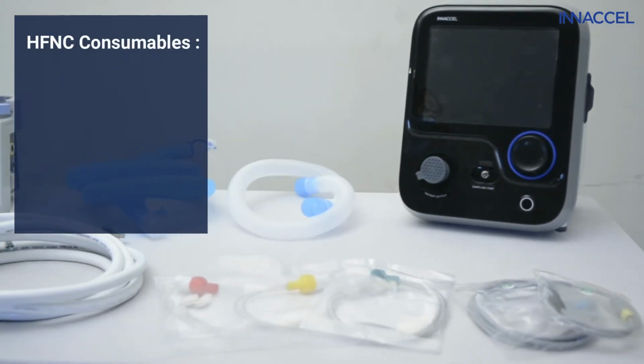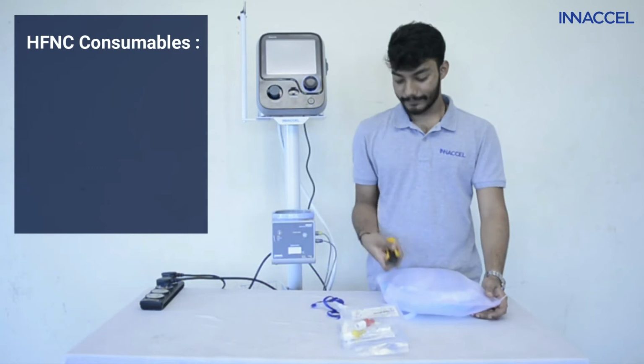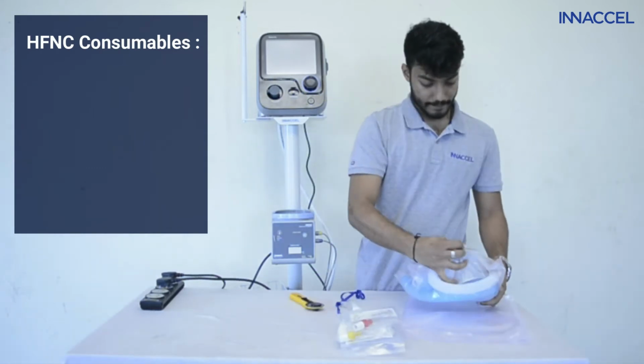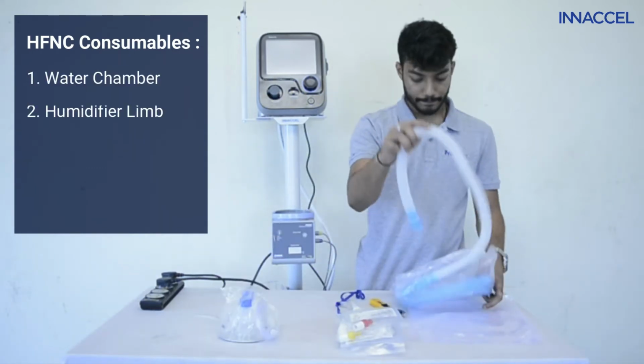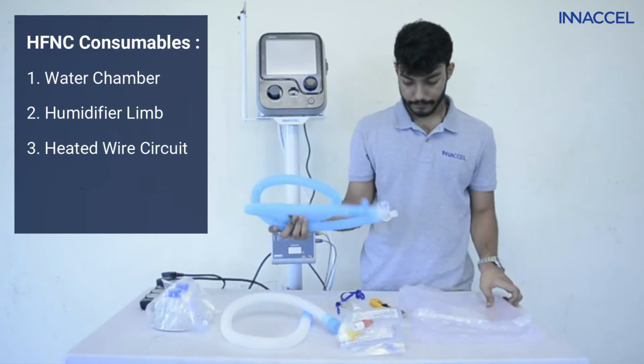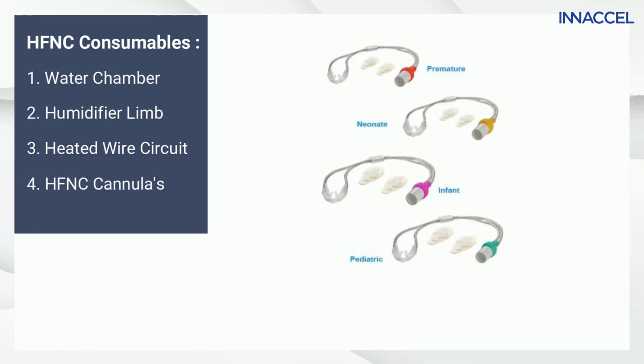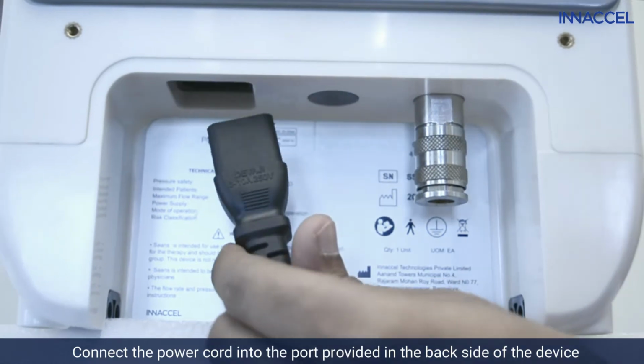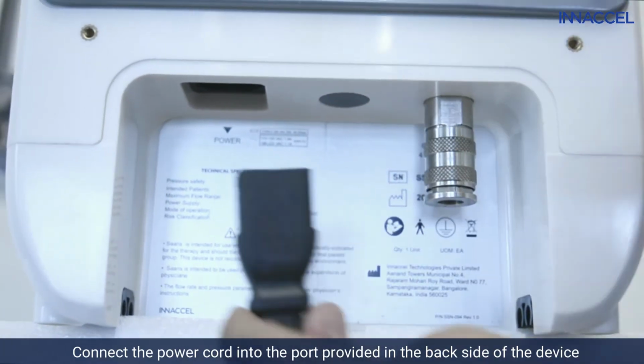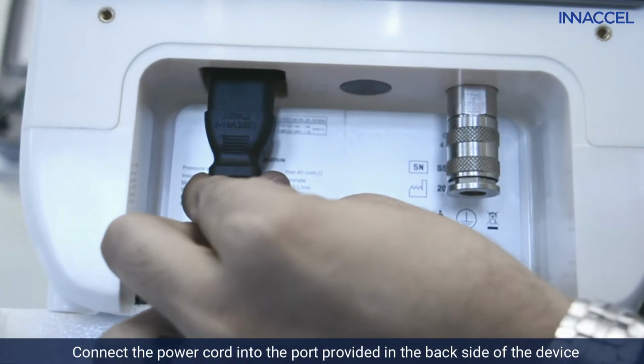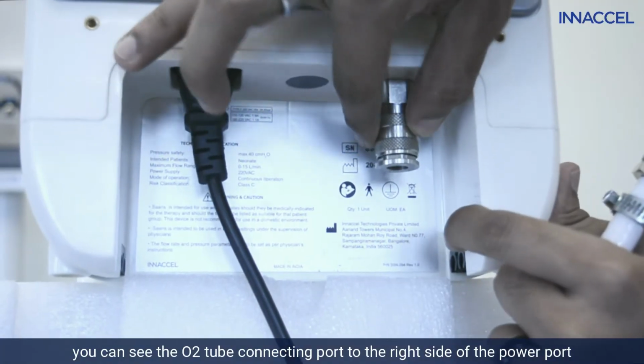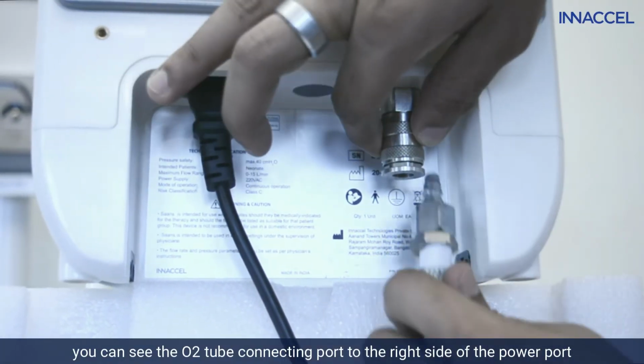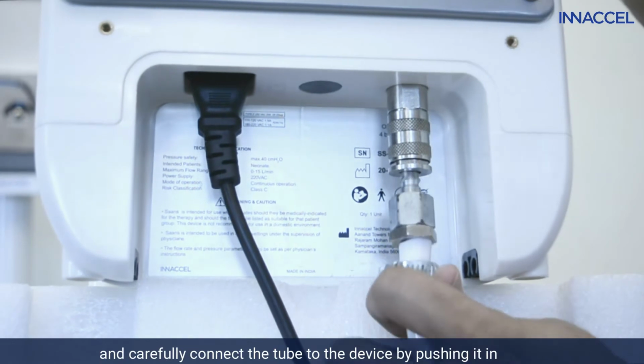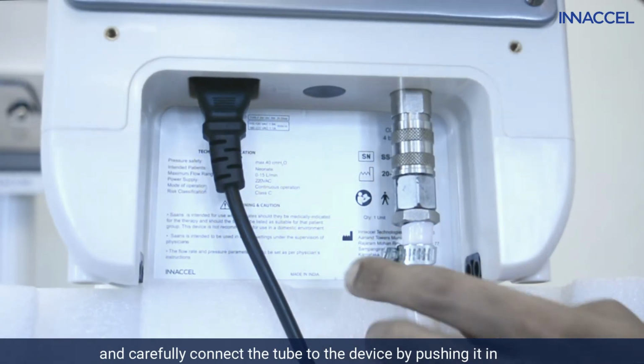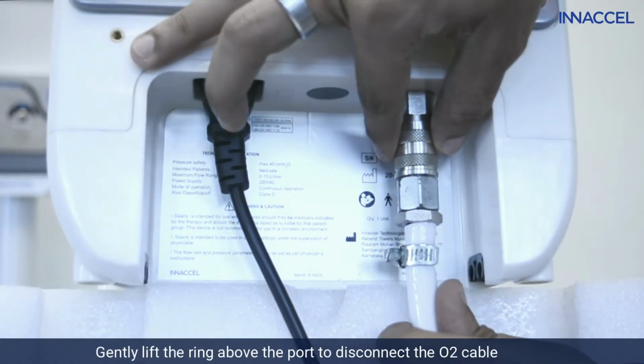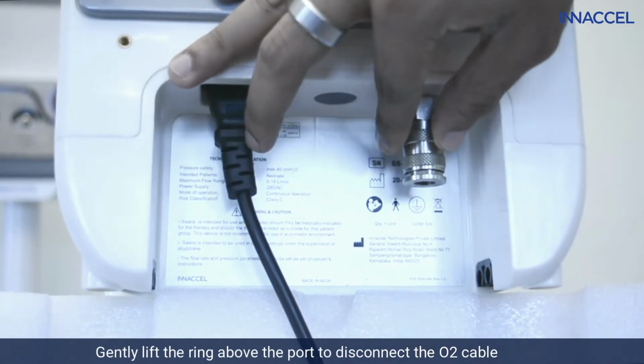Then open the HFNC consumables packet. It should contain the following components: water chamber, humidifier limb, single limb heated wire circuit, HFNC cannula. Now connect the power cord into the port provided in the back side of the device. You can see the oxygen tube connecting port to the right side of the power port, and carefully connect the tube to the device by pushing it in. Gently lift the ring above the port to disconnect the oxygen cable.